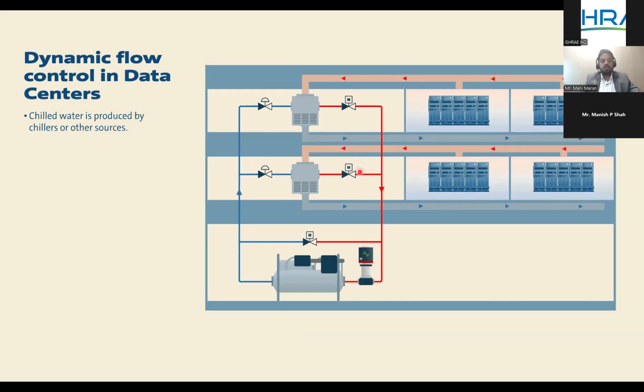And how does the functionality happen? When there is a change in the load, the feedback from the temperature sensor of the air side is given back to the valve, and this valve modulates to manage the flow, which is pushed by the pump, a centralized pump from your plant room. That's how we distribute the flow to multiple units connected in the secondary side.